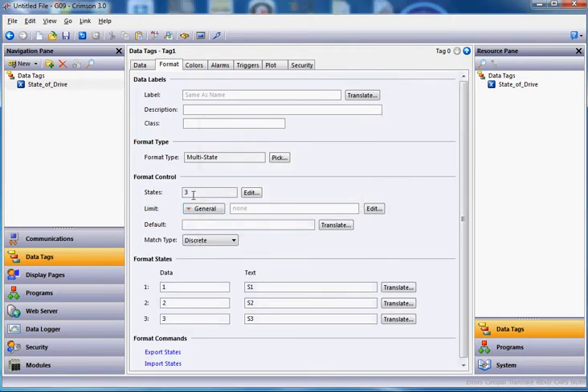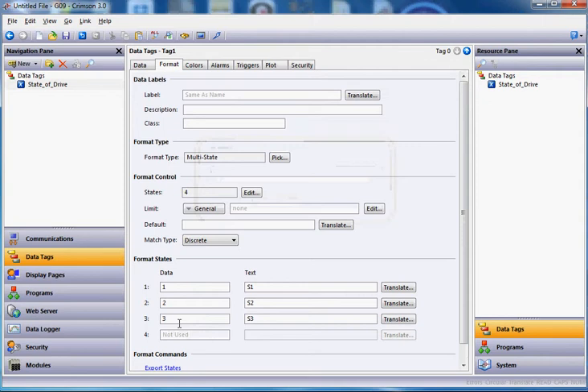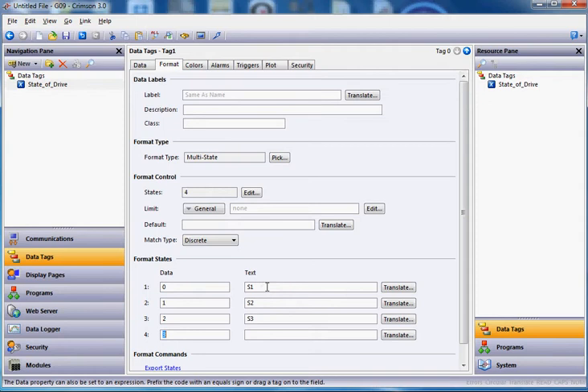You can see now that the format control says three states, but I'm going to have four states — stop, run, jog, and pause. So I'm going to hit the edit button and put the number four in there and click OK. Now I get four different states. I'm going to change the numbers to zero, one, two, and three. This text column is what's going to show up on the screen for the operator. So let's make it easier — put stop, run, jog, and pause as the labels for our drive control.